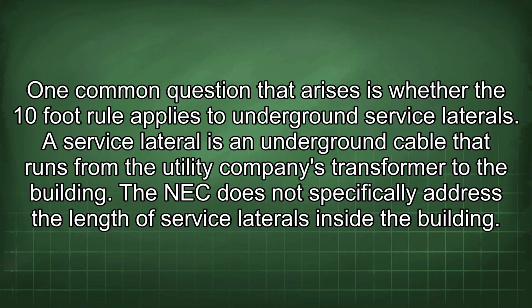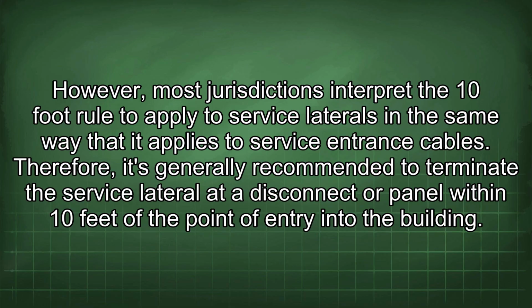One common question that arises is whether the 10-foot rule applies to underground service laterals. A service lateral is an underground cable that runs from the utility company's transformer to the building. The NEC does not specifically address the length of service laterals inside the building. However, most jurisdictions interpret the 10-foot rule to apply to service laterals in the same way that it applies to service entrance cables. Therefore, it's generally recommended to terminate the service lateral at a disconnect or panel within 10 feet of the point of entry into the building.